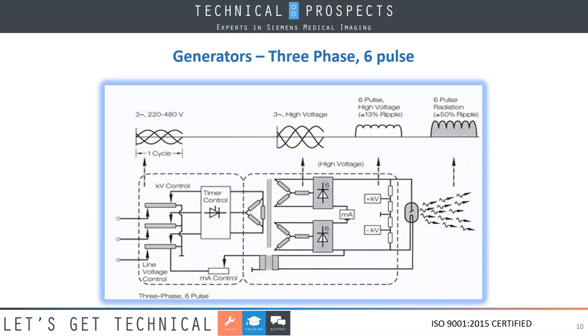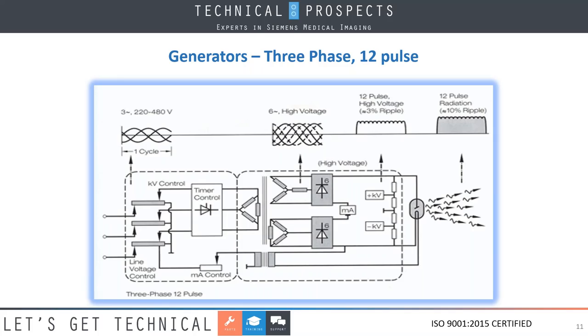Now, unfortunately, my computer jumped a second there, and you got to see the next slide, which is our 12 pulse. The primary difference between 6 pulse and 12 pulse you'll find in the secondary side of the primary high tension. Where on the previous slide we had a delta YY configuration, now in the secondary here you see a Y and delta in the secondary. These two different transformers in the secondary create an additional 30 degree phase shift on the AC power, hence when we rectify it, it gives us a 12 pulse and a smaller ripple, and therefore a higher quality KV.